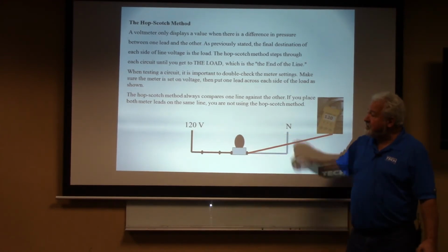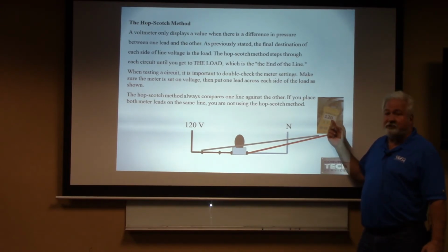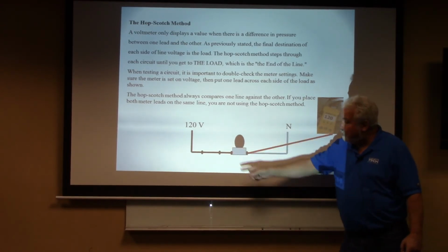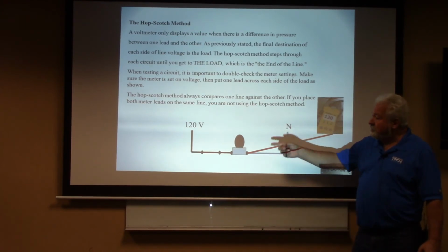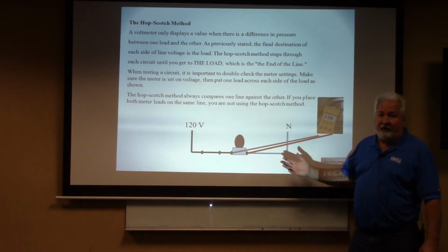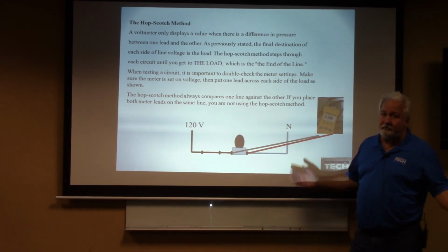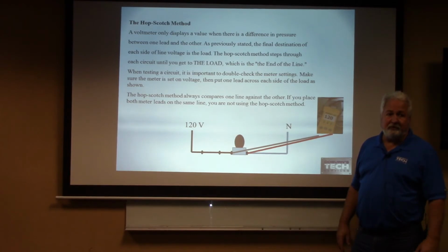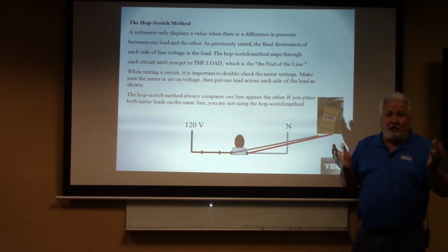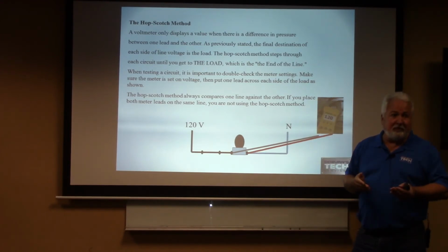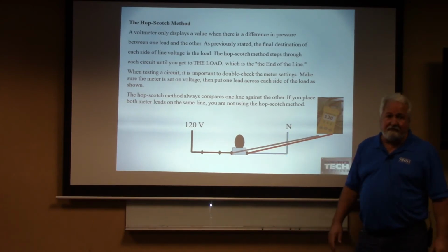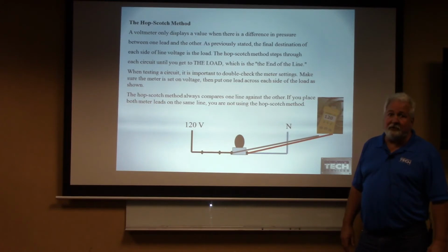Does that make sense to you guys? Good. Then I'm going to just take it in one step at a time. Do I have voltage there? Yes. Do I have voltage there? Yes. Do I have voltage there? Yes. If I have voltage to the load and the load doesn't work, poor load. Does that make sense to you guys? Good. It's called the hopscotch method. Sometimes when you start getting lost on a job site, just go back to the basics. Step it here. All you're trying to do is get that voltage to the load. Is that right? Find out where you're losing your voltage. In this particular case, we've got voltage to the load. If you got voltage to the load and the load doesn't work, bad load. Good? All right.